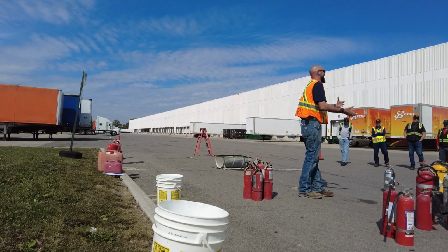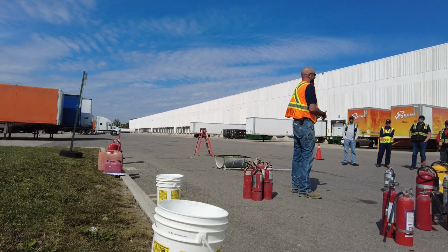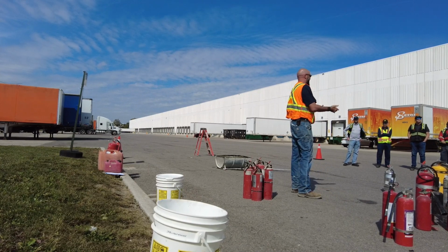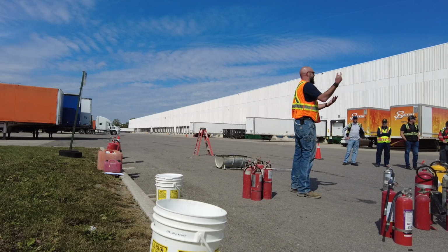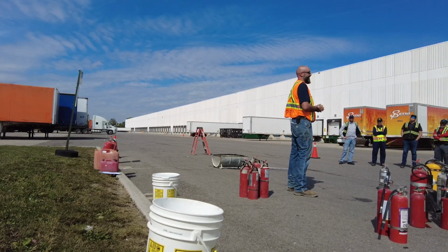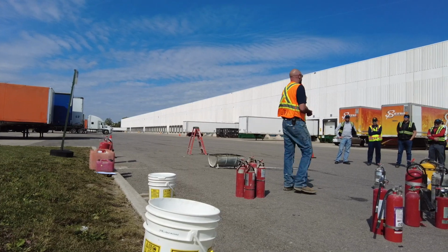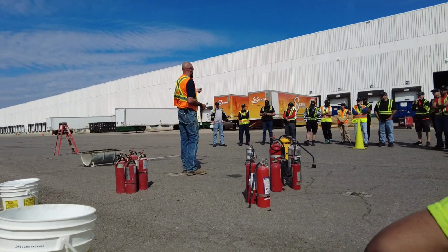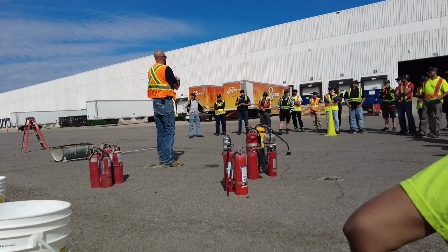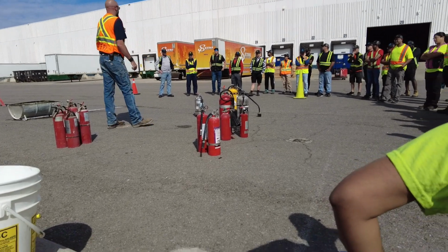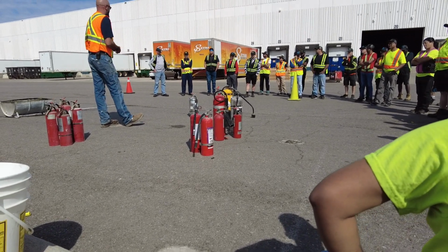The reason is that nitrogen will leak out, and there will be no more pressure to push the chemical out. So basically, if you hang it back on the wall, you've just put a piece of art up there, because it's not a fire extinguisher anymore. How does it leak out? Because the powder that we use is extremely fine, it's almost like talcum powder, but the nitrogen can seep out around through that powder around the O-ring once it's contaminated.